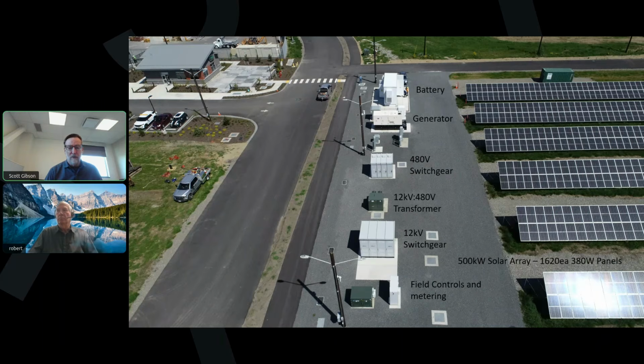That's what's caused us the most issues over the last 6 months, transitioning from grid following to grid forming. The vendor recently figured out a way to just always keep it in grid forming mode, so we've switched to that 100% of the time, and now the system seems very stable. Knock on wood, theoretically our maintenance is going to go way down while we focus on making the system function as a backup power source.